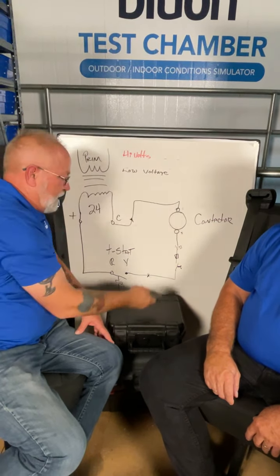When you reestablish the power, your high voltage comes back and your low voltage comes back. You still have that signal, but you've erased the ghost voltage. You also reboot the controller a bit. A lot of the air conditioning units nowadays, it's not the old electromechanical devices, contactors, relays, and all that other kind of stuff. It's a lot of data.